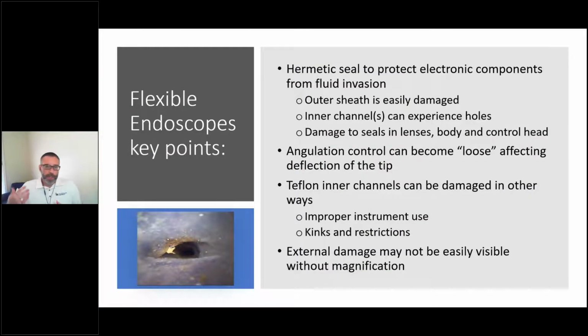Now we'll switch, just as Jahan did, to flexible endoscopes. Guess what? They're also hermetically sealed. They have electronic components and areas that are not accessible for cleaning. If the seal is broken, the electronics can be damaged. And it's not just water that can get in there - blood and other fluids too. So bioburden and contaminants can get in there.